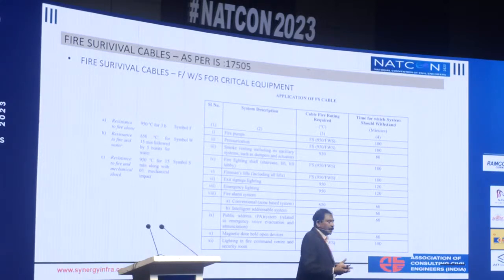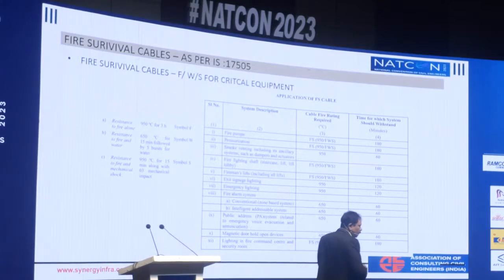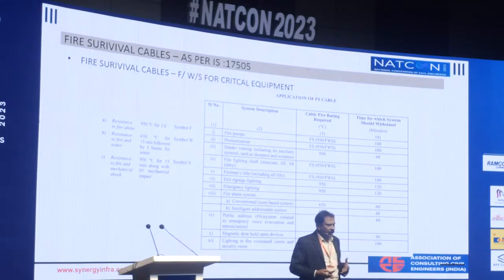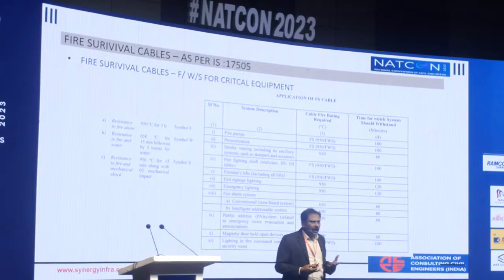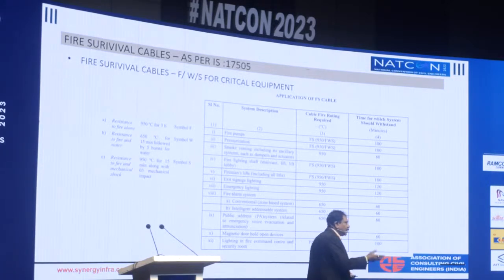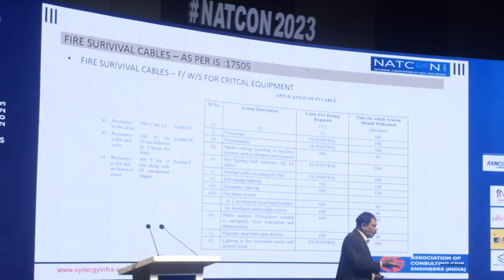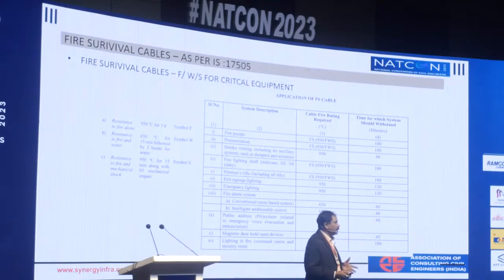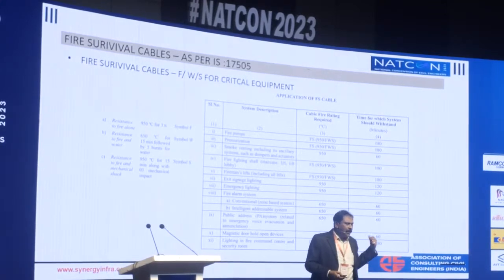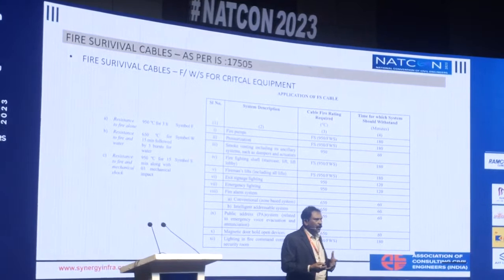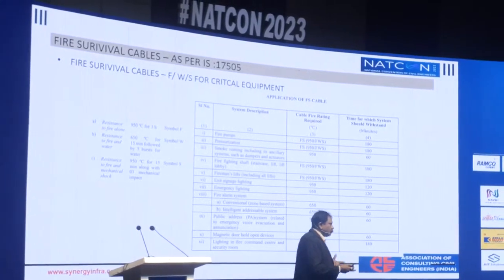They have to withstand 950 degrees centigrade of temperature for a duration of either 180 minutes or 120 minutes, depending on the purpose of it. So the F indicates basically the fire withstanding capacity of the cable, 950 degrees centigrade, and W is basically fire and water. Generally what will happen when there is a fire, immediately there will be a burst of some water poured onto that. We have to have electricity in any kind of building. We can't cut off the whole power for any building because there will be a lot of mechanical systems which also have to work in the suppression of fire and the smoke.